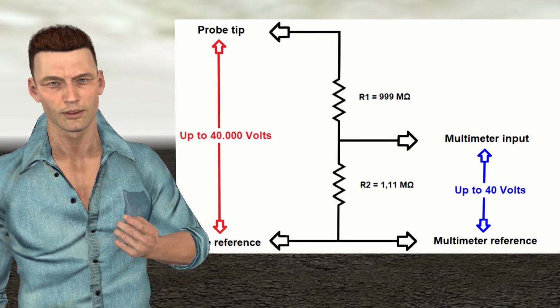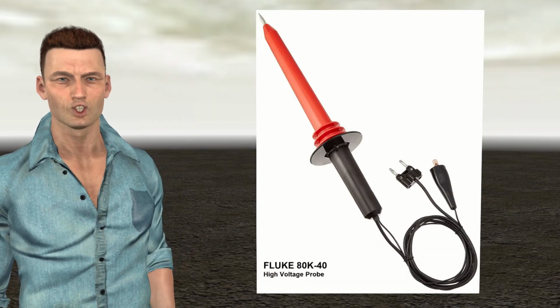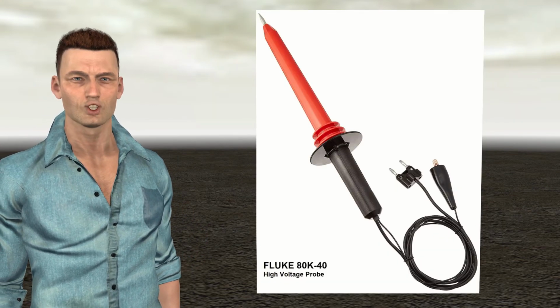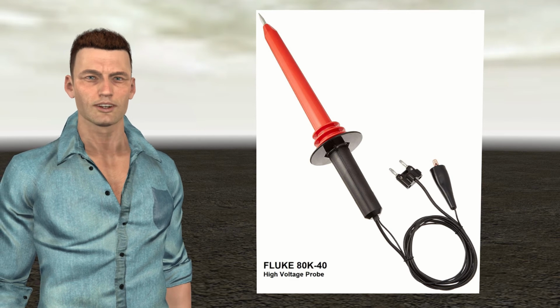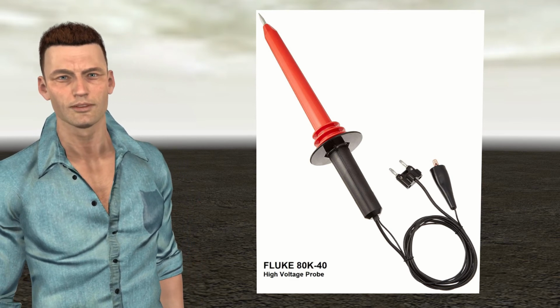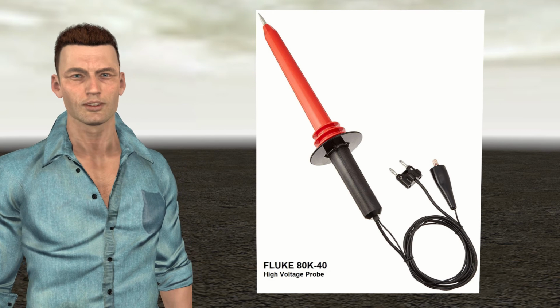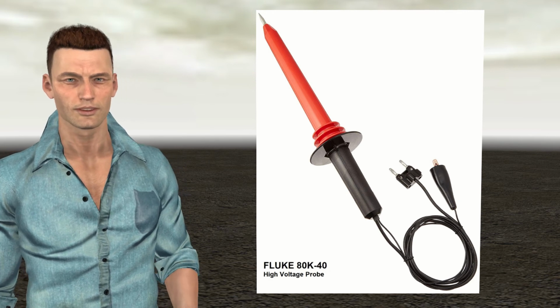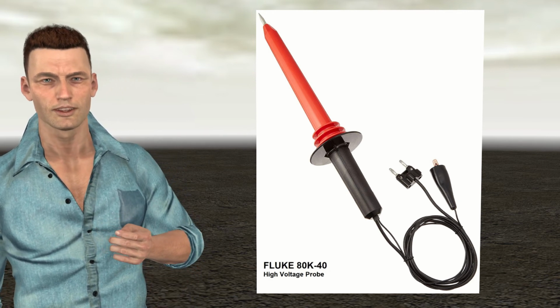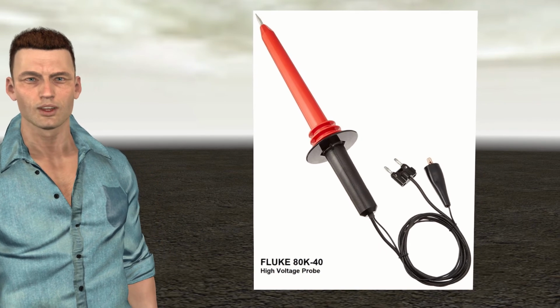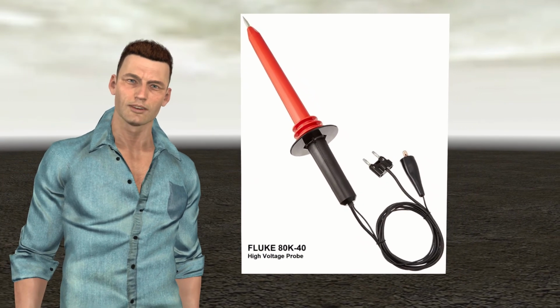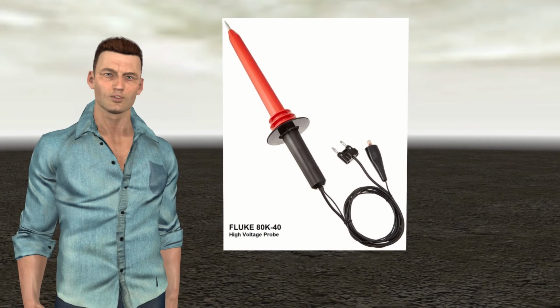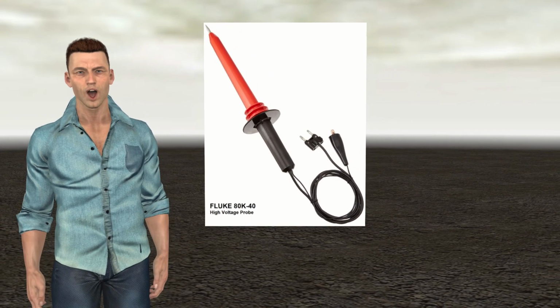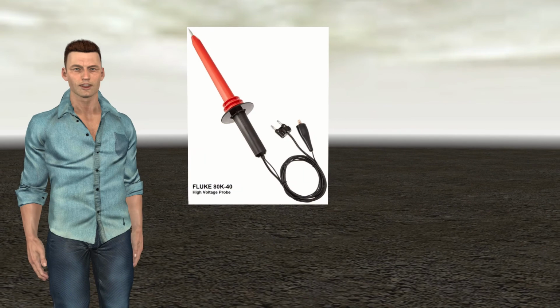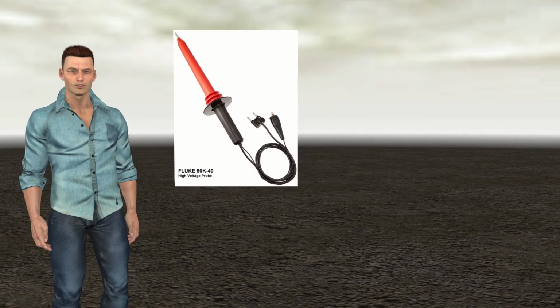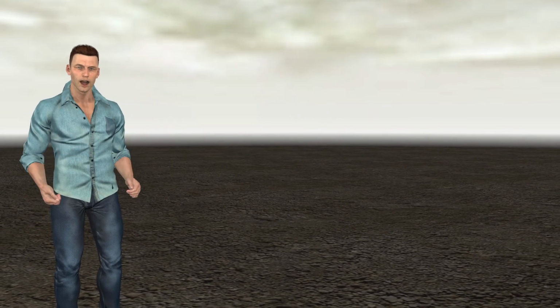The use of this type of probe is very simple. We see that it has a long tip that we must apply to the high voltage circuit and a crocodile connector for the high voltage reference, and on the other hand, it has a double banana connector that we connect to the voltage input of the multimeter. We select AC or DC in the multimeter depending on the voltage we want to measure, and if the multimeter is in auto range mode, it will directly show the value on the display. If it is not auto range, we will have to select the appropriate range, dividing the range of the high voltage to be measured by the attenuation ratio of the probe.